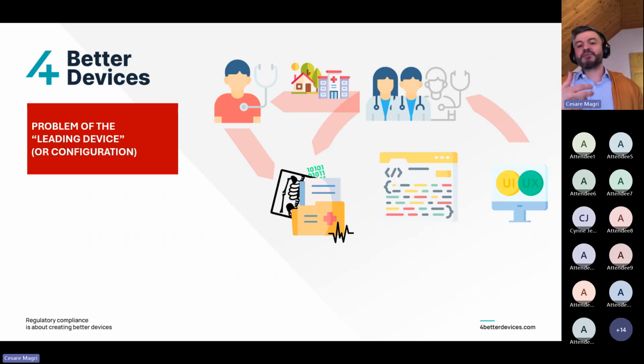So one first step could be, I'm not specifying a certain type of device, but I'm specifying the parameters that should be satisfied by the input and by the user interface. This is still possible. It's not easy, and the problem with it is that you have, first of all, to be very precise in the way you characterize these input and output properties, and still remember, in the moment you go and try to certify the device, the notified body will ask you for the validation of this device, and it's impossible to validate the device in any form unless you test it with one of the specifications that you gave about the input and output.